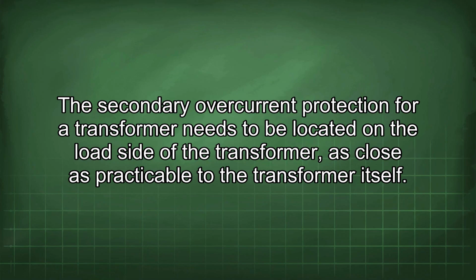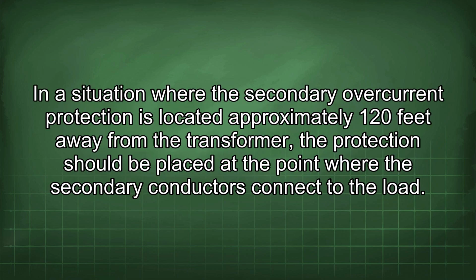Secondary overcurrent protection for a transformer needs to be located on the load side of the transformer as close as practicable to the transformer itself. In a situation where the secondary overcurrent protection is located approximately 120 feet away from the transformer, the protection should be placed at the point where the secondary conductors connect to the load.